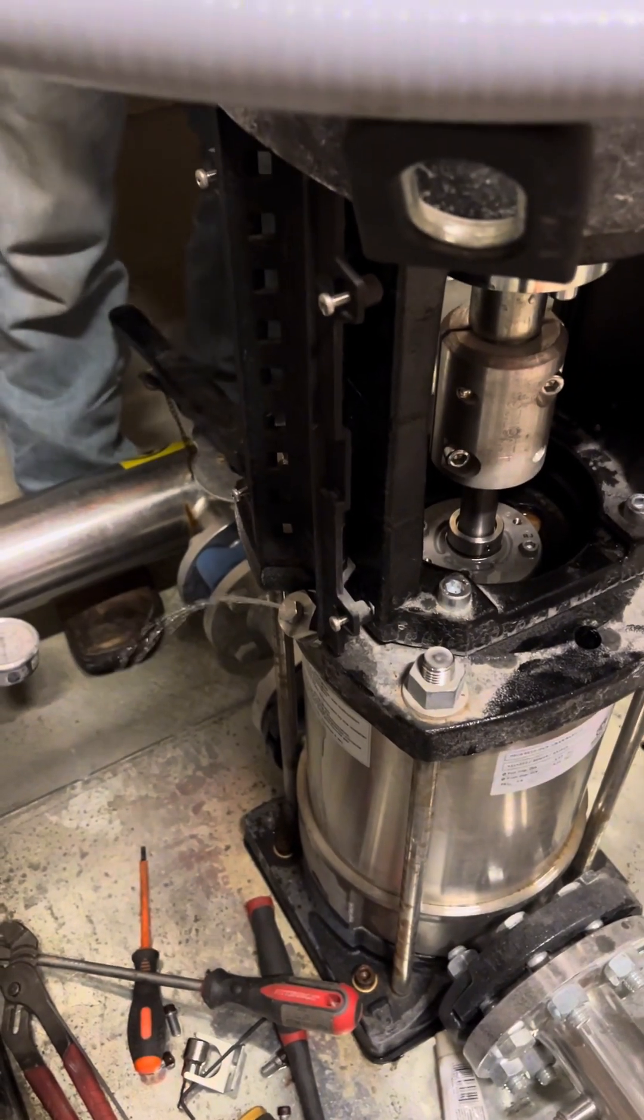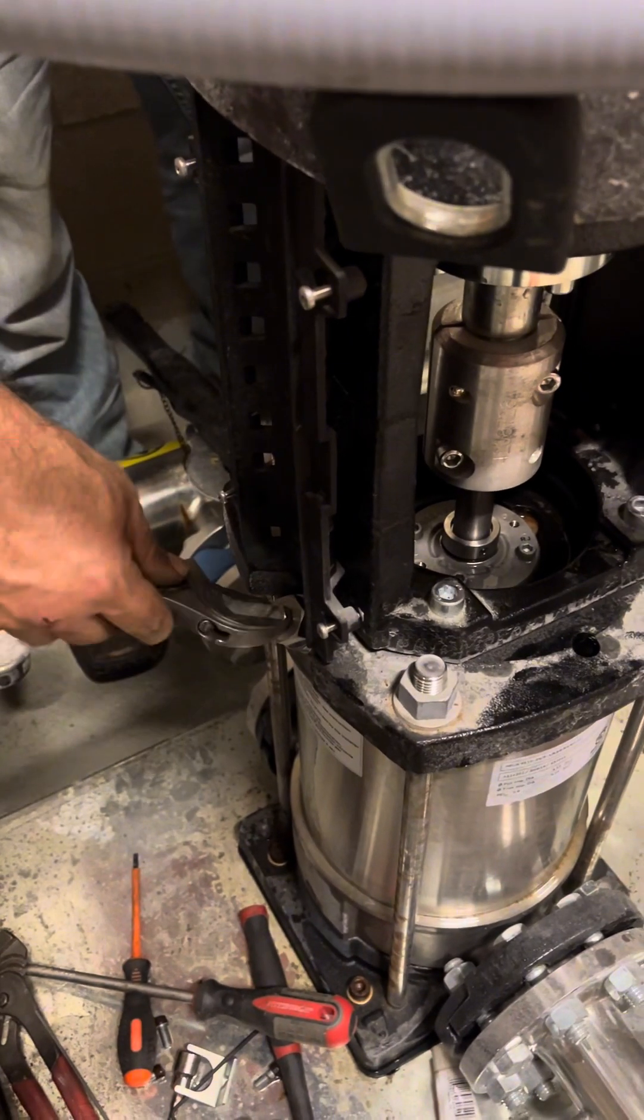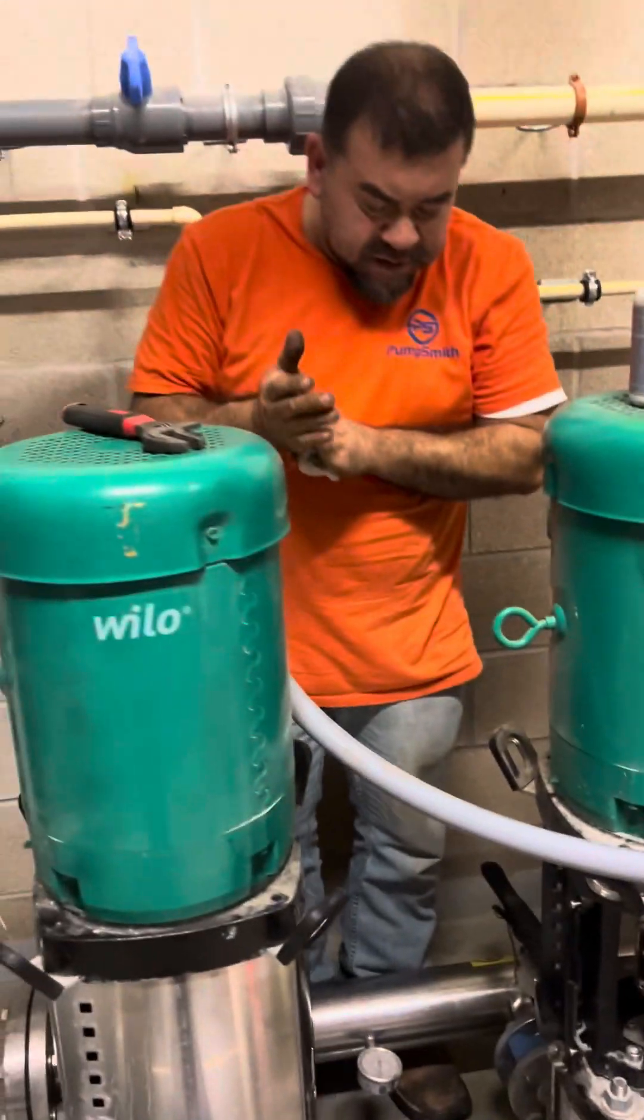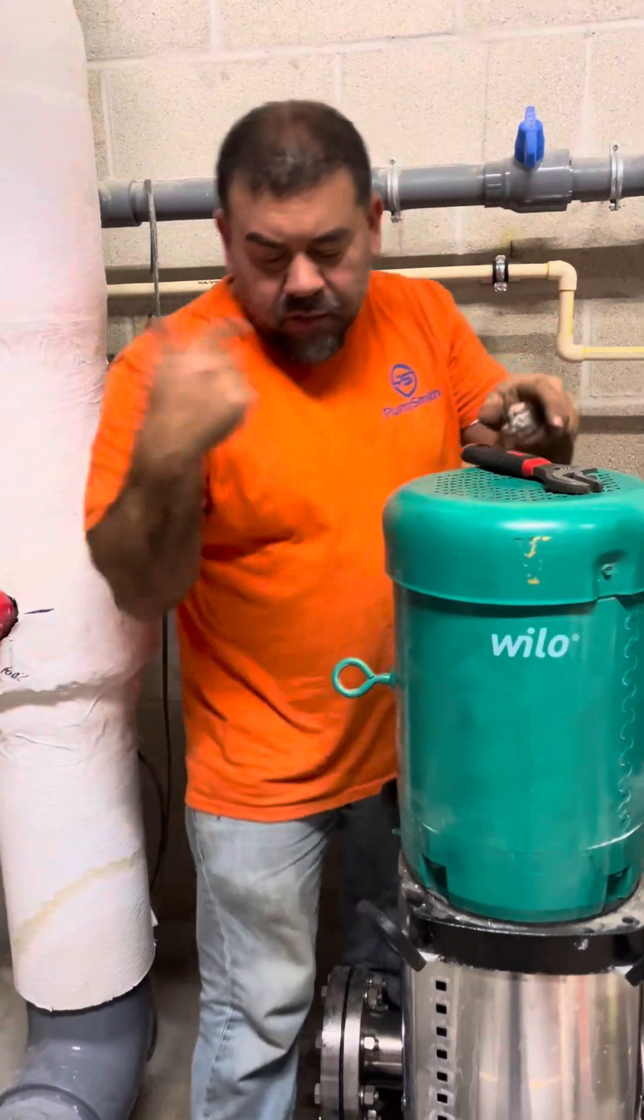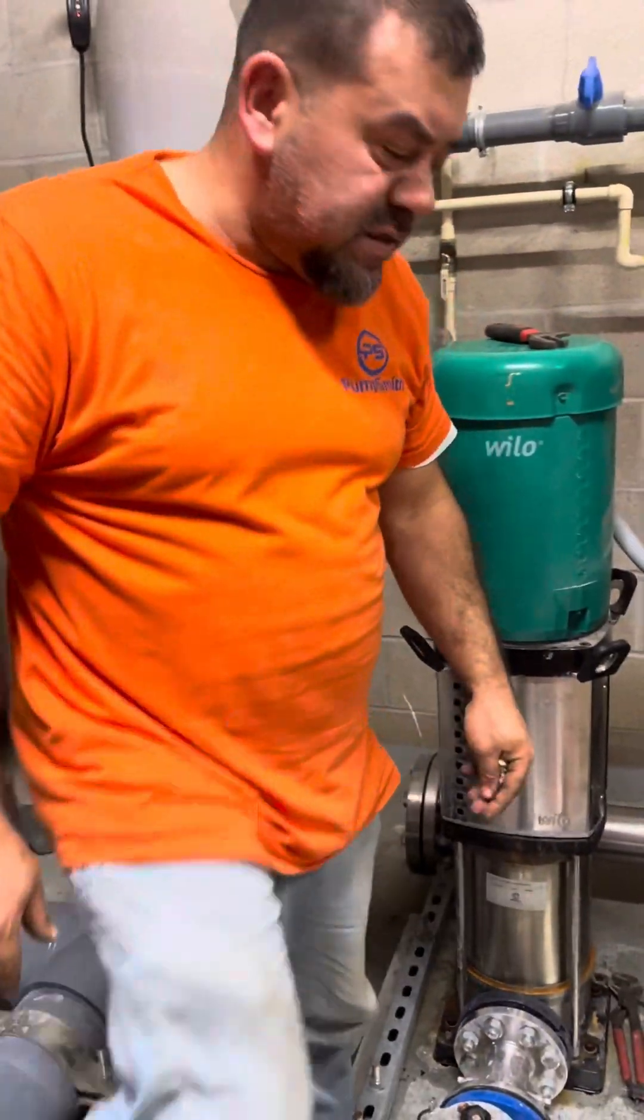Sometimes when you put a new seal in there, it will still leak a little bit until you start running the pump, because those two surrounding surfaces are touching each other but they're not quite even. Once you start to do that rotation, they'll settle up and be flat, pushing up against each other.